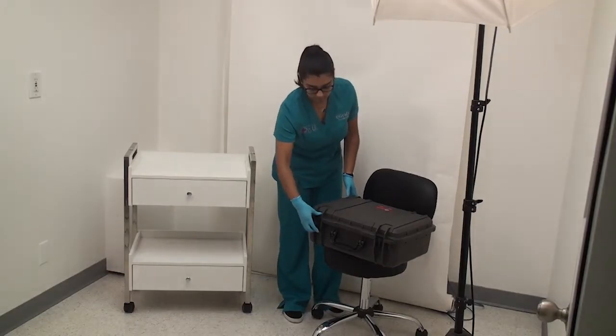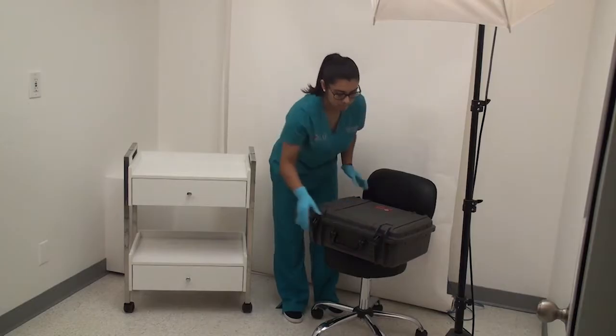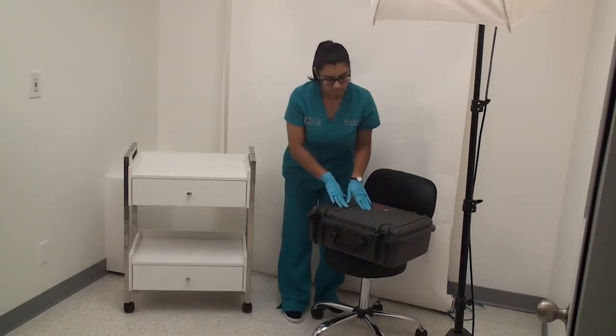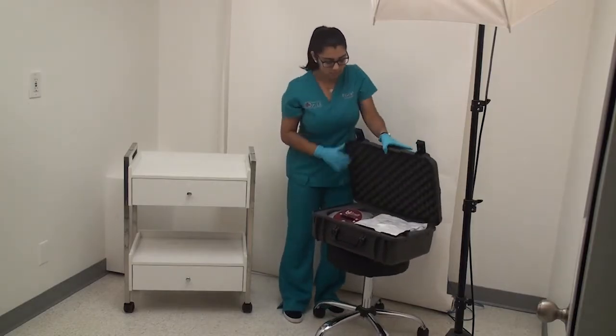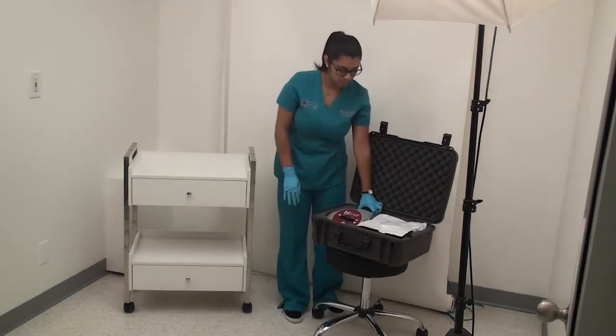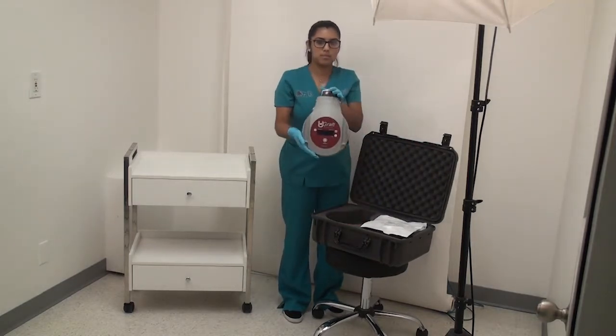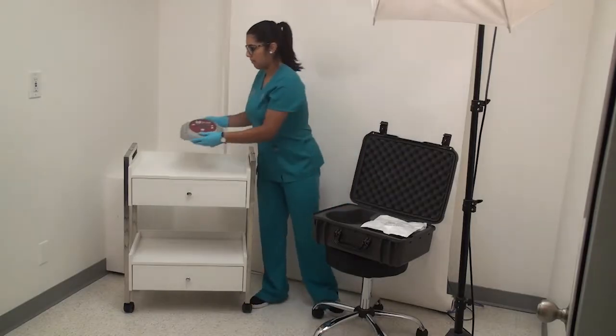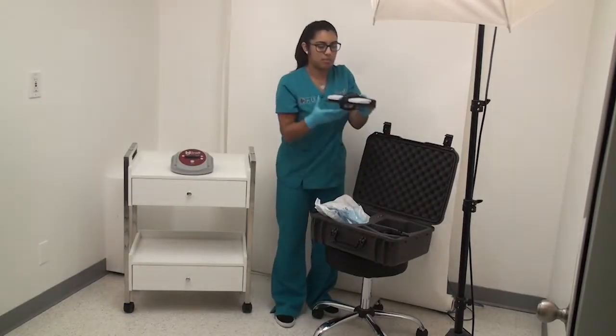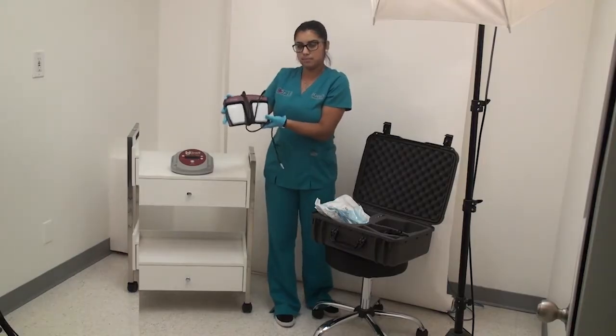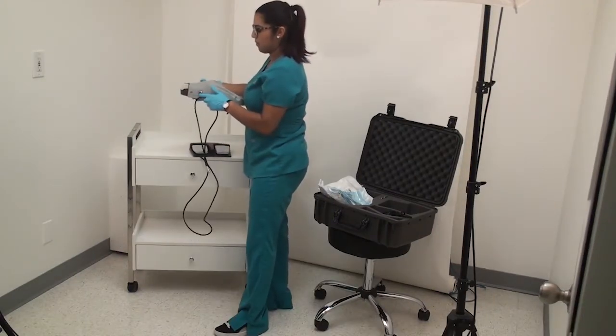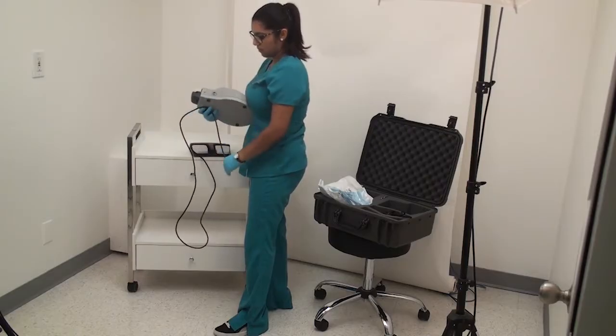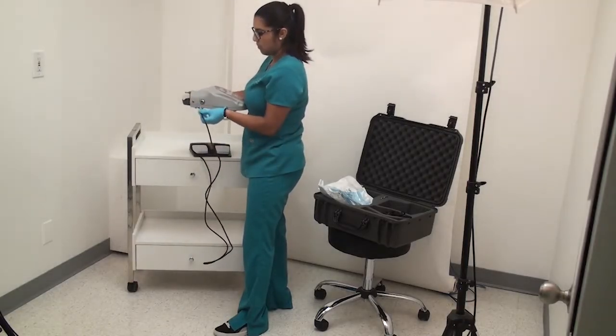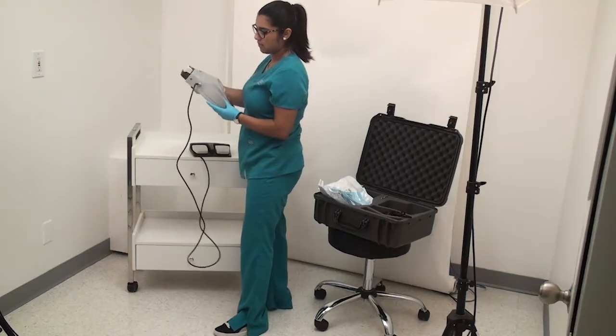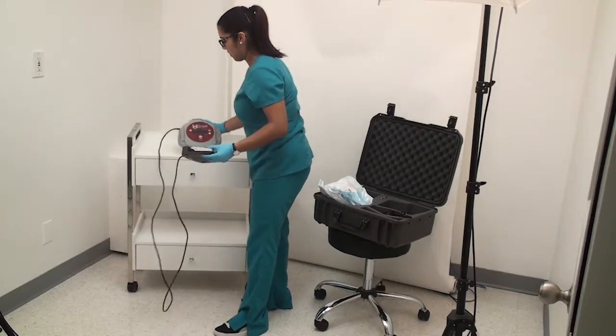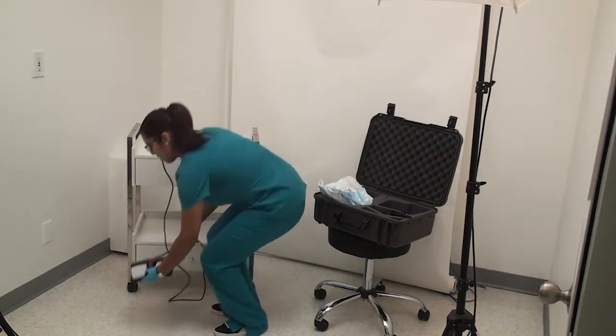To assemble and set up the Dr.UGraft hair transplant system, you ideally need a table or a cabinet. A mobile cabinet would be preferable to set up the system. Start with the console. Then, the foot pedal. Connect it to the port on the right of the console. It goes into the bigger port. Place the foot pedal on the floor, close to where the operator's foot would be.